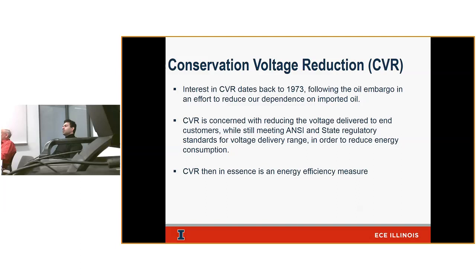CVR is concerned with really reducing the voltage delivered to the end customer while you continue to meet the ANSI code and the state regulatory standards for voltage delivery range. That would end up, in theory, reducing the energy consumption. We talked a lot through the first four lectures about loads, our ZIP models, and how loads do react to voltage.